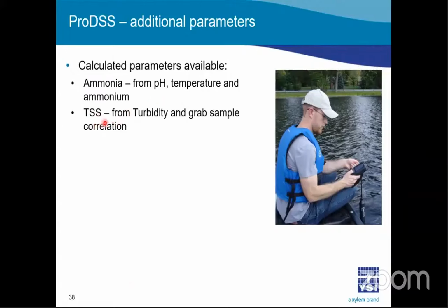Total suspended solids is actually calculated from turbidity along with a grab sample correlation factor. So you need to do a bit of work when you want to measure TSS — you need to do a grab sample measurement and calculate the correlation factor with the turbidity readings.